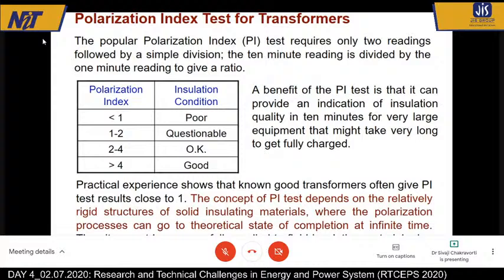You ask anybody working in Calcutta Electric Supply, West Bengal State Board, any engineer will tell you what a PI test is. This is very simple, done by an instrument called a Megger. So you take that instrument and measure the insulation value at two different conditions: first at 1 minute and then at 10 minutes. Now, we will get two readings.